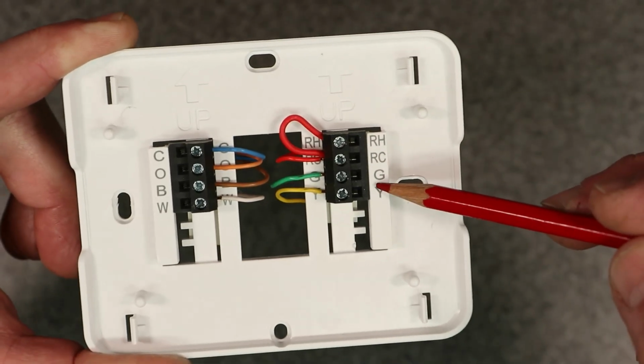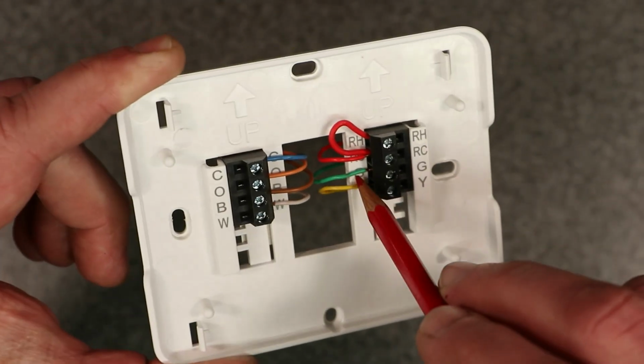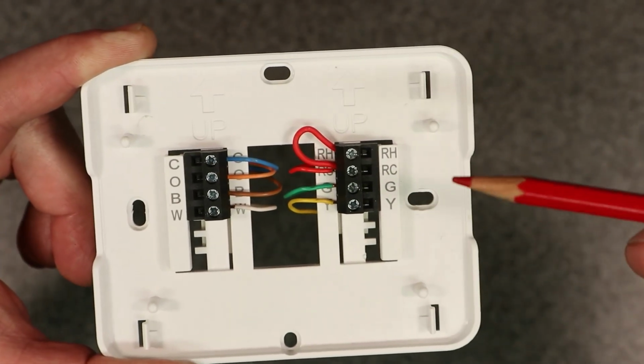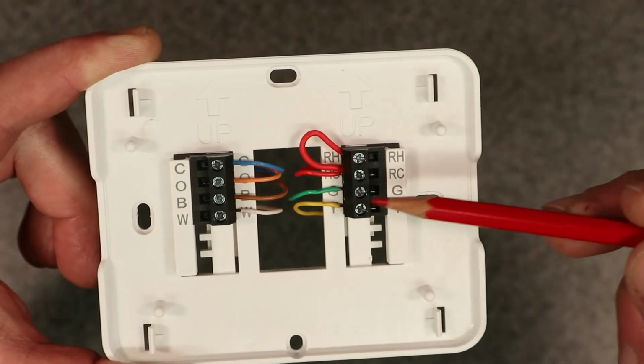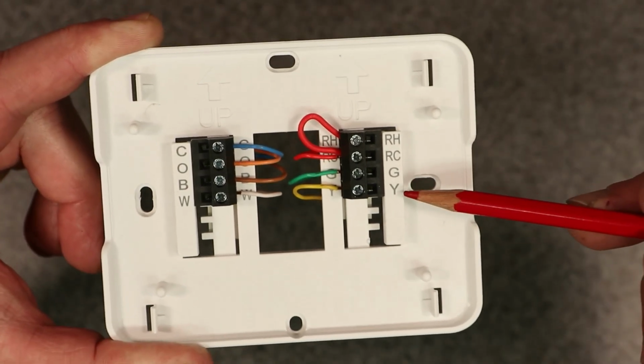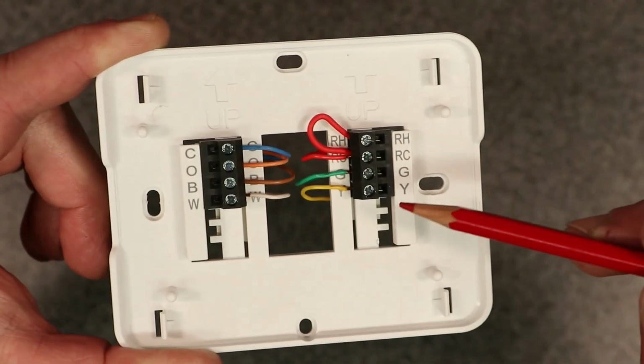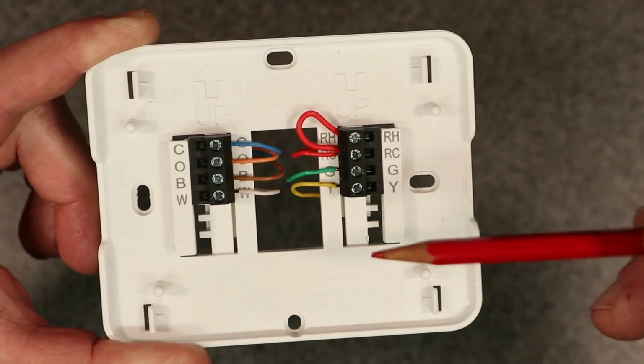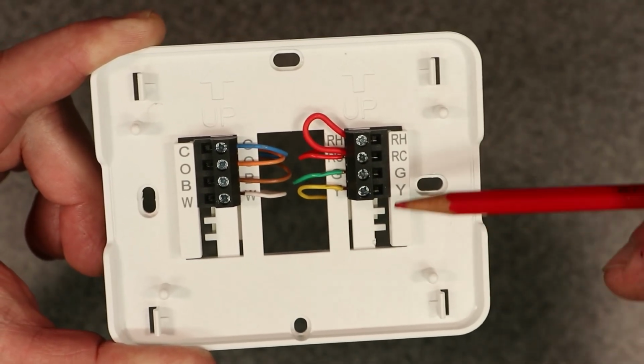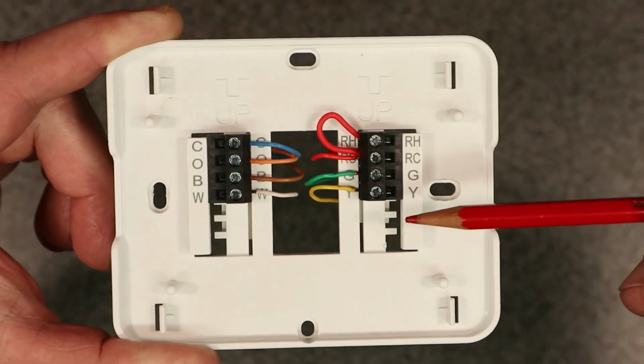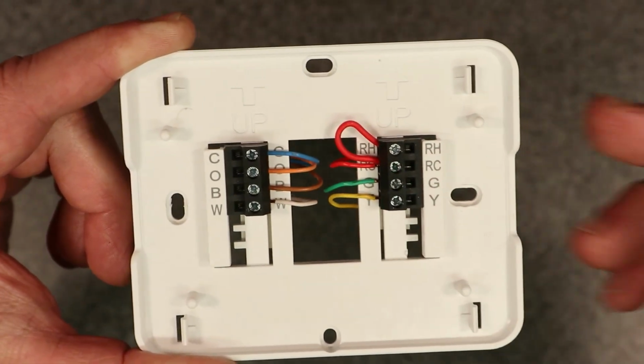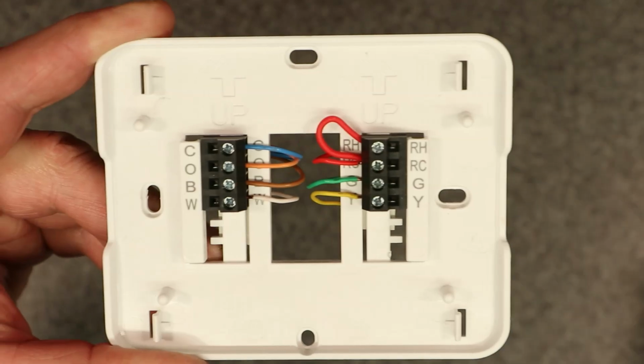The next one is green, which is the G terminal, green wire, and that's for your fan, okay? You want to hook that up if you have a fan in your system. That's very important. The next one is the Y terminal, which is your yellow wire, and that is for your first stage cooling, okay? Very important to have that hooked up for first stage cooling. But that there is the basic rundown on all the wires on this very simple Amazon thermostat.